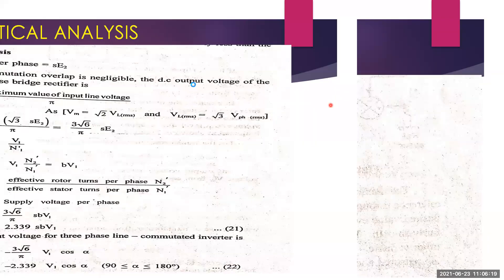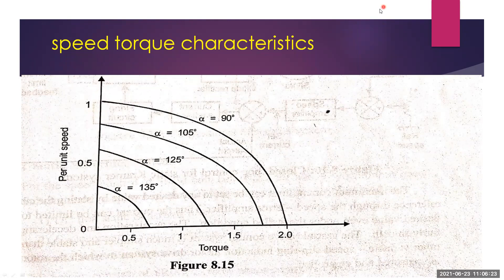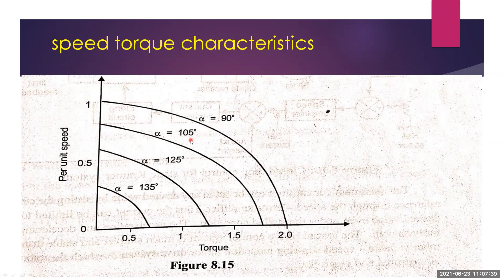The speed-torque characteristics of the static Kramer drive for an open-loop system for different firing angles are as follows: by varying the firing angle — for example, alpha equal to 90°, 105°, 125°, and so on — the speed versus torque characteristics change. These characteristics are similar to a separately excited DC motor with armature voltage control, showing a small droop.